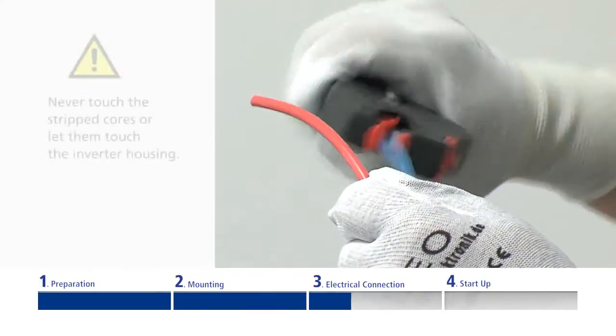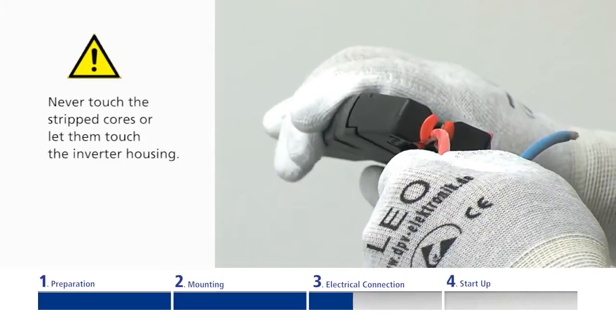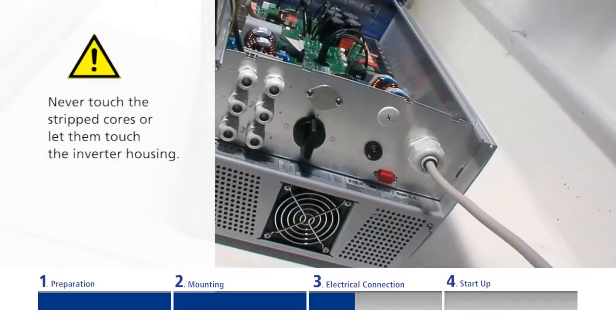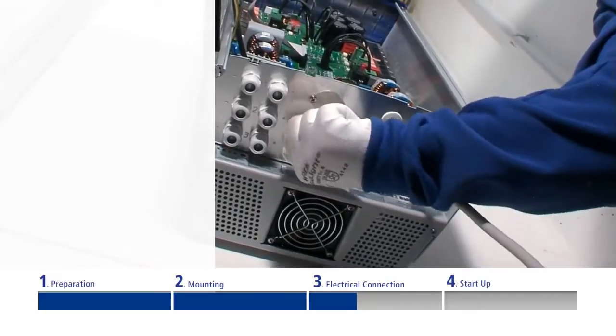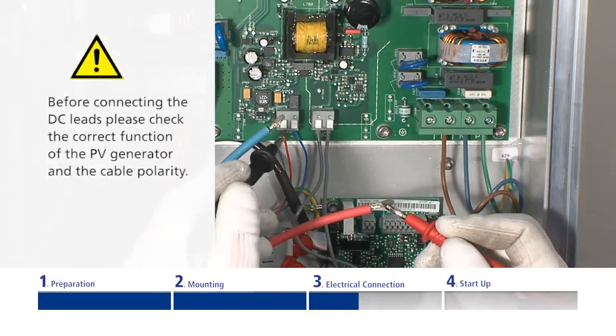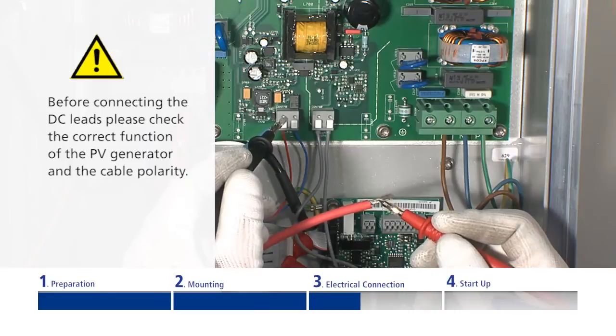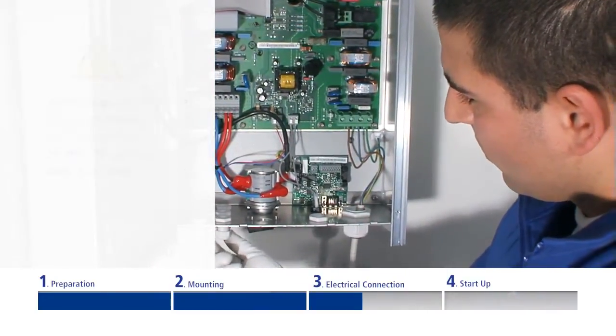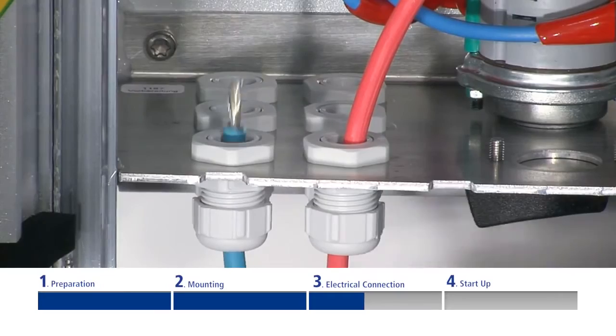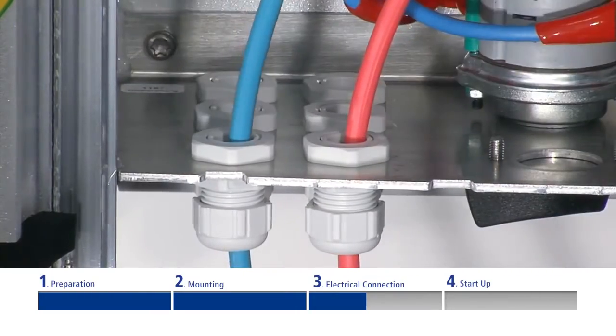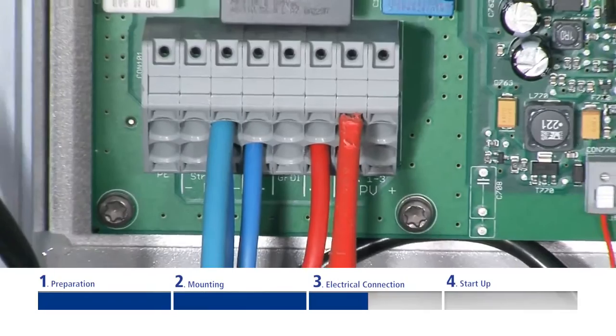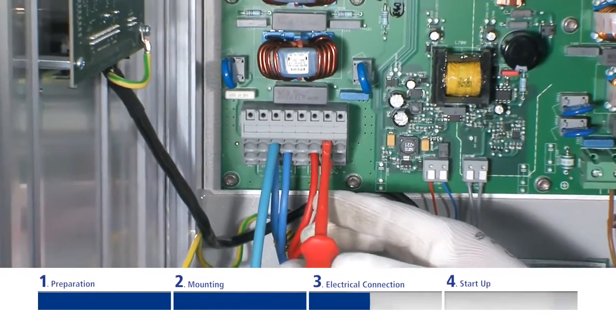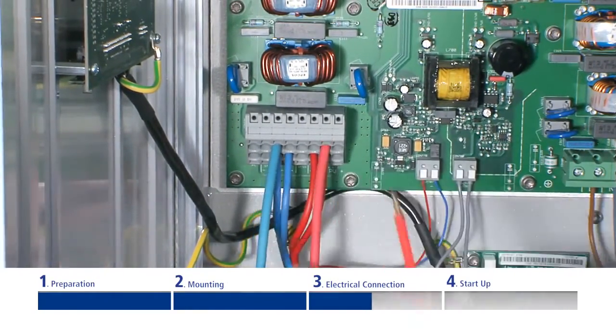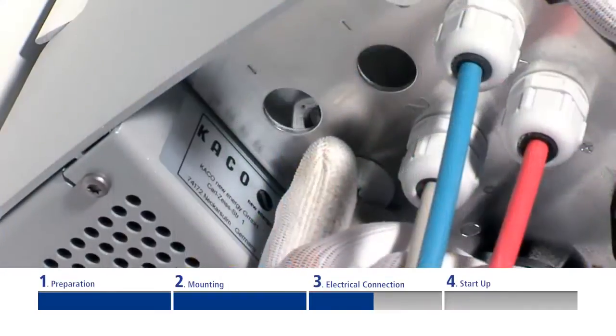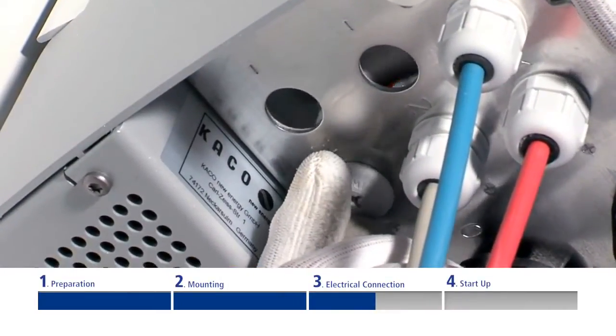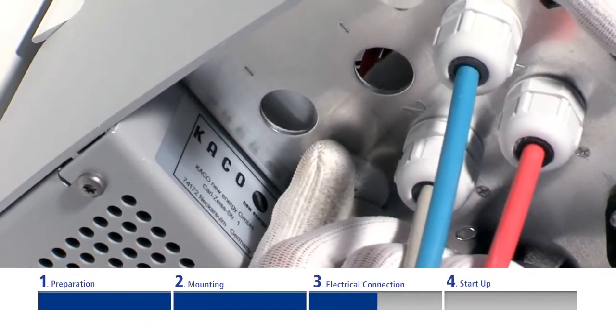Afterwards, the DC lead of the PV generator is connected. Ensure that the integrated DC disconnector is switched to the off position. Check the polarities with a measuring gauge. Secure the cable ends into the connection terminals. Pay attention to the PV plus and PV minus signs. Connecting to the wrong pole will damage the inverter. Tighten the cap of the cable fitting. Unused cable fittings must be closed off by using the protective caps which are included.